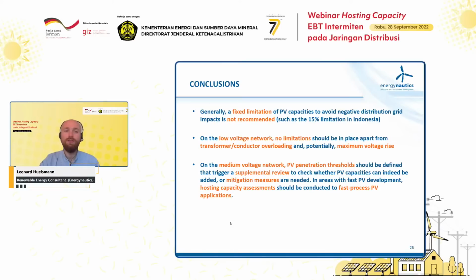A final conclusion is that we generally do not recommend having a fixed limitation of PV capacities, which includes this 15% limitation in Indonesia. Rather, on the low voltage network, there should be no limitations in place apart from transformer and conductor overloading, and potentially maximum voltage rise limitations, as well as further screens such as requiring certified equipment. So in terms of fixed limitation, we say you shouldn't have one except for the general transformer and conductor loading limits. On the medium voltage network, PV penetration will eventually lead to impacts there too.